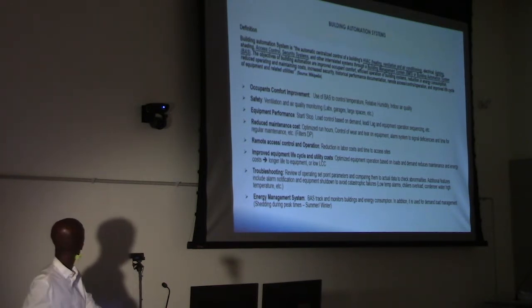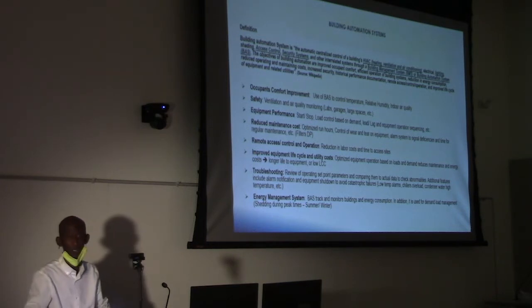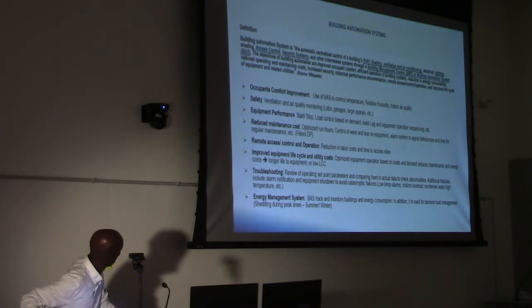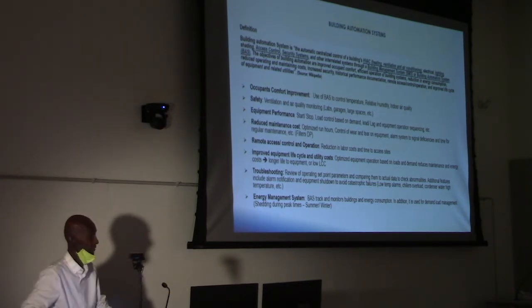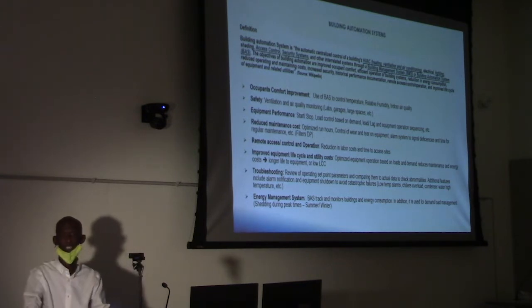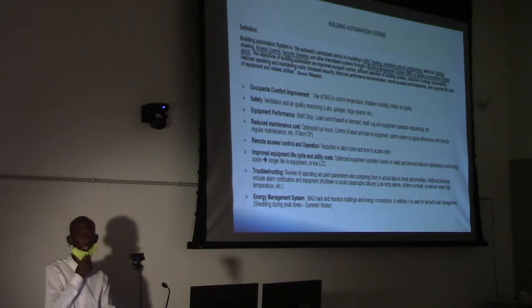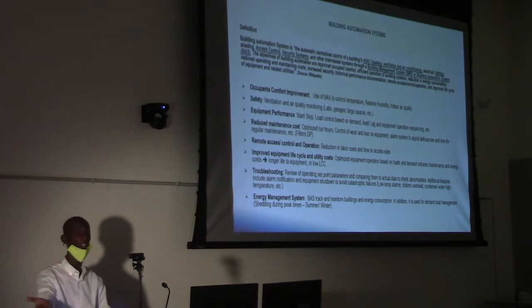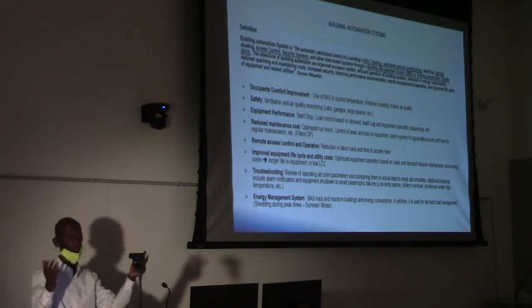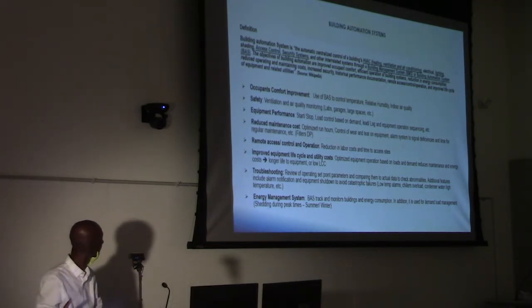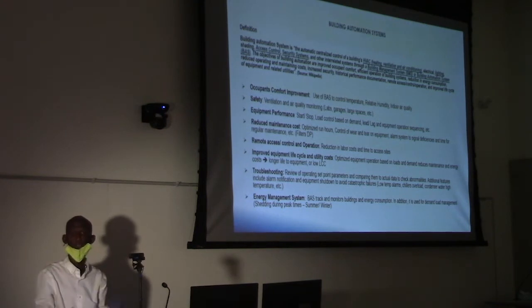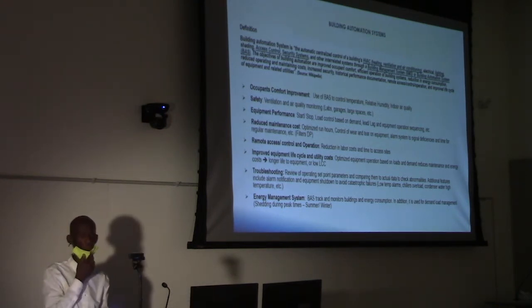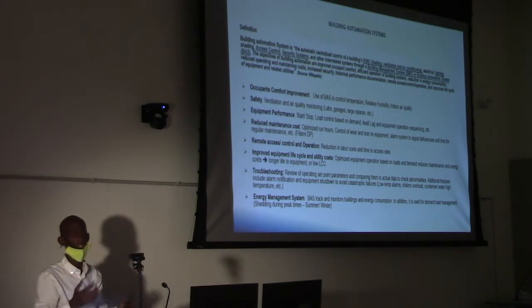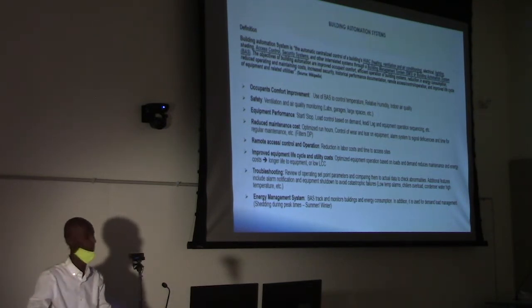Same as here on campus, we try to start and stop the equipment based on the occupancy, whenever we can. The next one is load control based on demand. Sometimes, we may have huge demand, summertime for instance, if we are cooling and the temperature goes from 60 in the morning to 95 degrees, we have to be able to ramp up our chilled water systems so that we can satisfy the demand. And vice versa, when the temperature goes down, we lower the speed, we decrease the flow of the chilled water so that we can meet the demand.